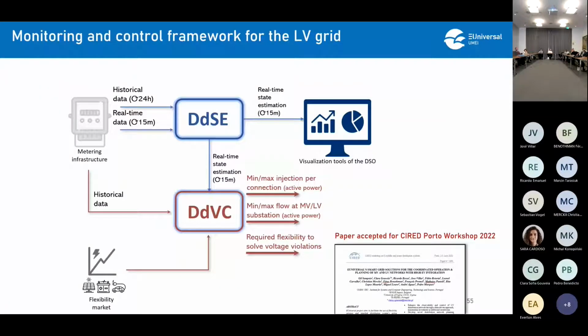So we have two tools: a data-driven state estimator and a data-driven voltage control. The data-driven state estimator can run every 15 minutes; I say 15 minutes because here in Portugal that's the resolution of our smart meters, but it can be any other resolution. This results in outputs, the most likely state of the system, which can be visualized by the DSO or can feed the data-driven voltage control. And if there is an over voltage or under voltage, the data-driven voltage control can run and try to solve it, using, for instance, flexibility offers from the market as input.